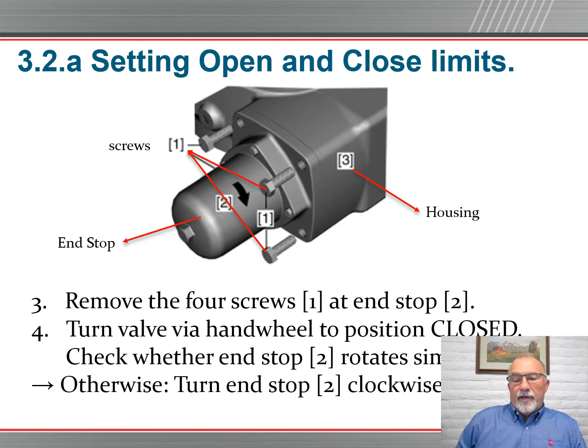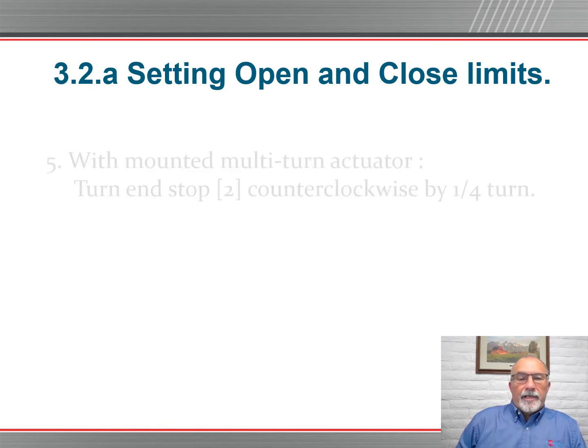Turn the valve via hand wheel to position closed. Check whether the stop rotates simultaneously. Otherwise, turn the end stop clockwise to the full stop position by hand. Then replace your bolts, and your close limit switch or limit stop is set.